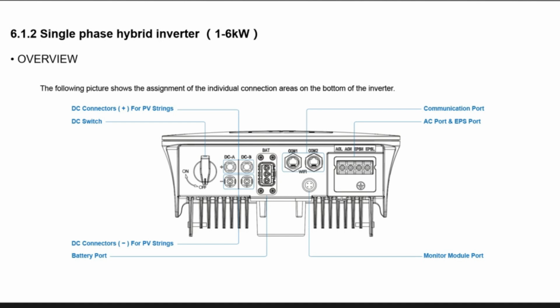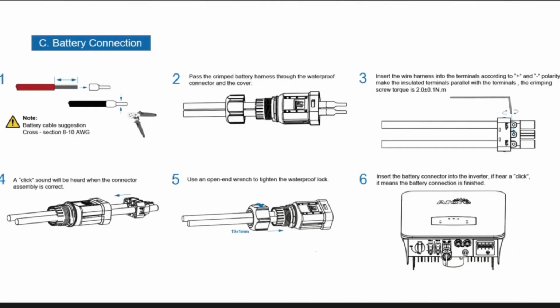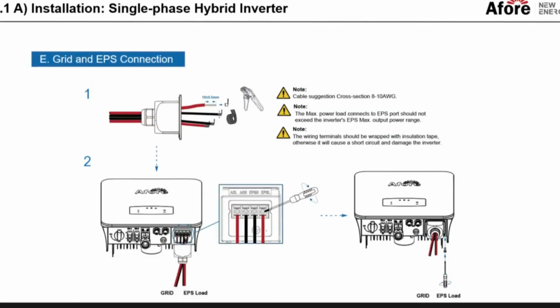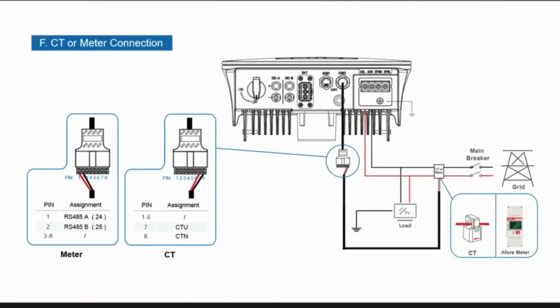If you're using a CT, on the back of this, but you can actually cheat. Wherever the cable comes out the side of it, the side that the cable comes out is the side that points towards the fuse board. So towards the home rather than pointing to the grid. That's essential that you put it that way around, because otherwise it will be reading the imported electricity as PV generation. So if you get it the wrong way around, it'll charge and discharge the batteries. The white one goes into number 7 on there, and then black goes into number 8.